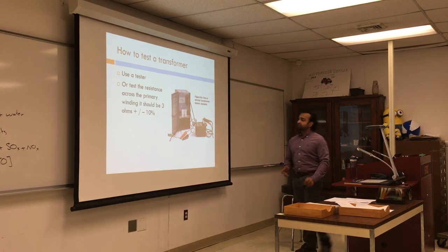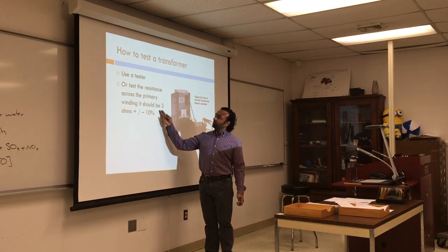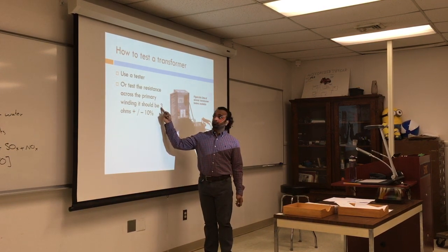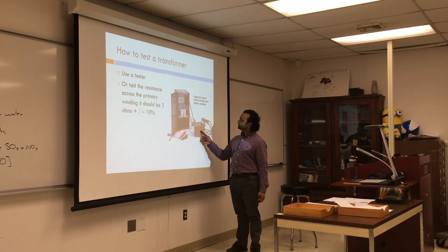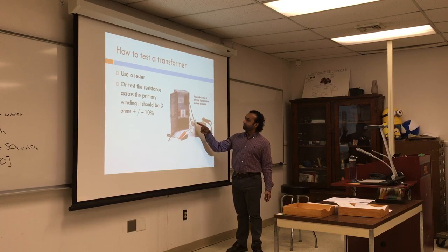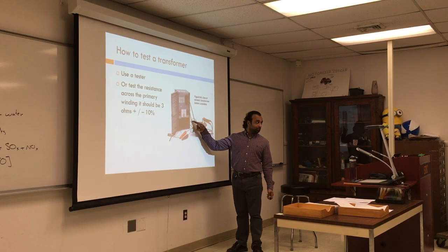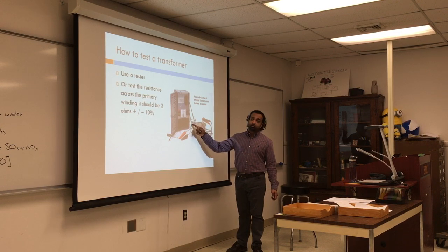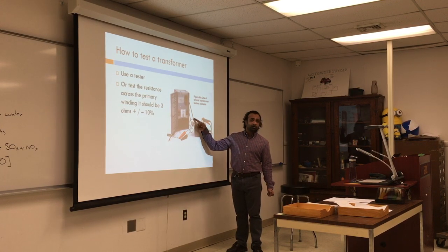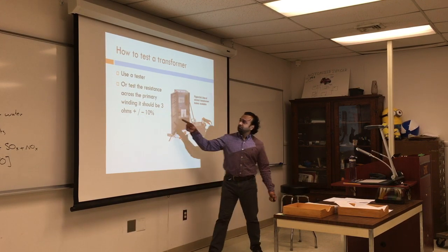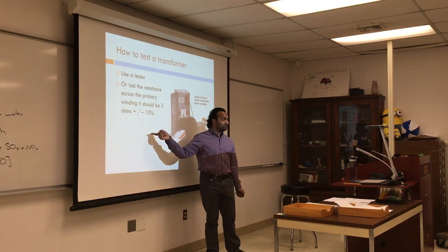So you can test the resistance across the primary winding. Should be 3 ohms. What is the primary in this case? Here or here? Which one? This one, the 120. So you test the resistance across the primary. Should be around 3 ohms, plus or minus 10%.